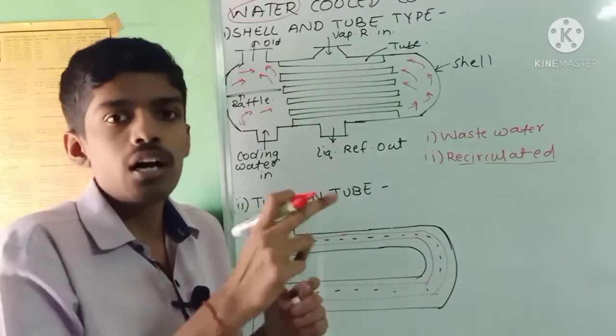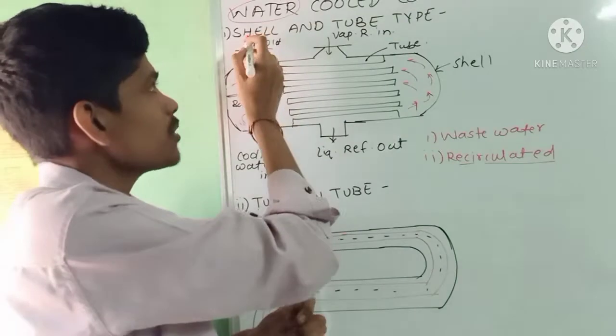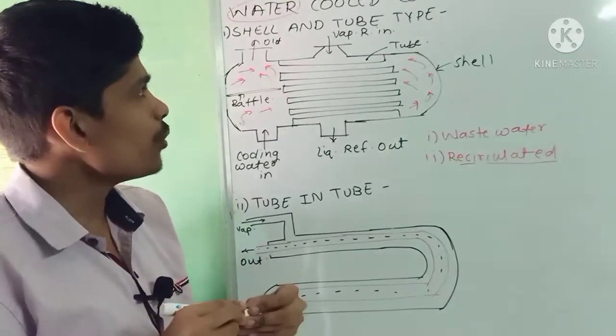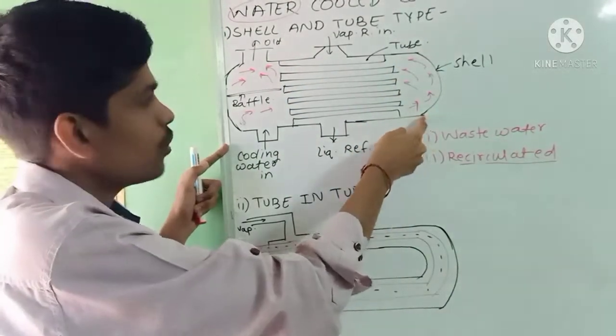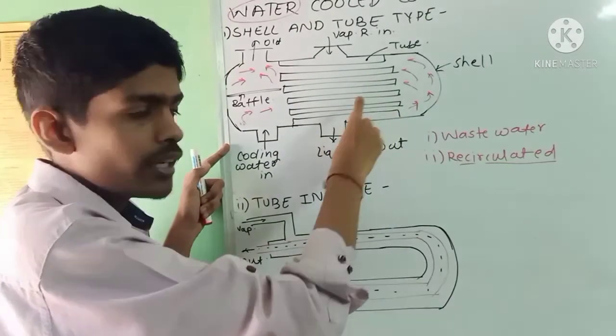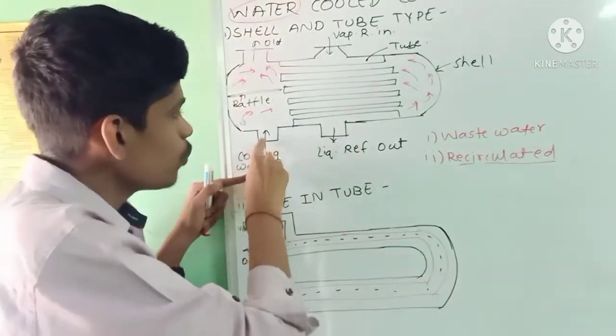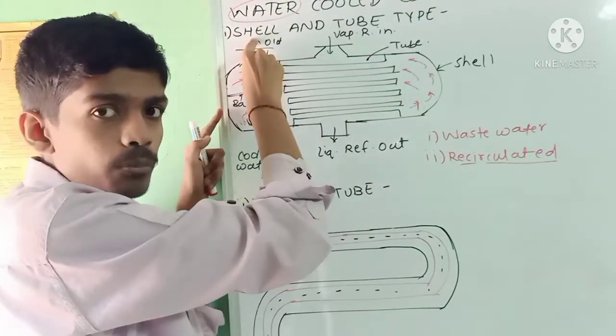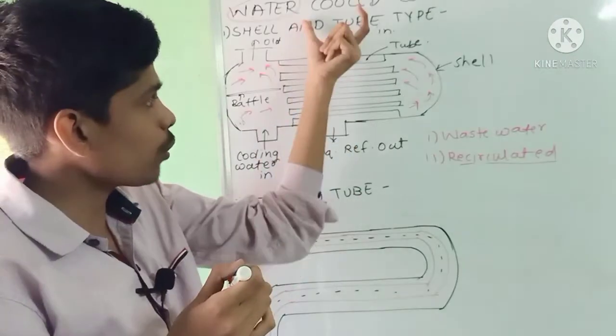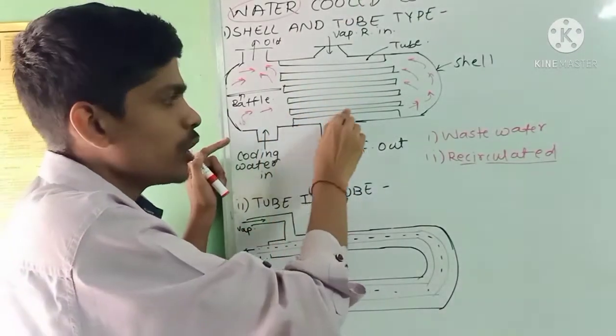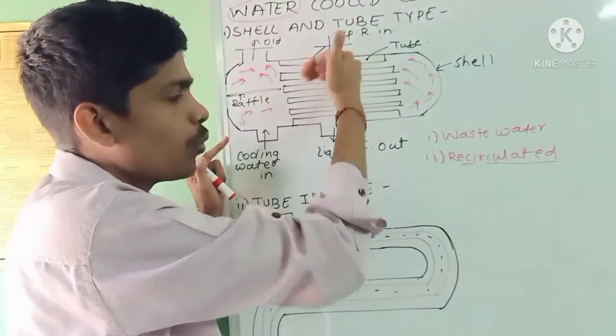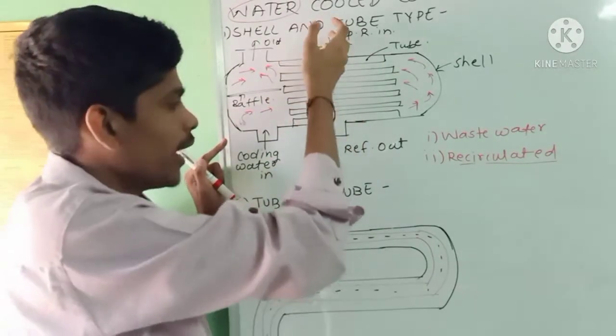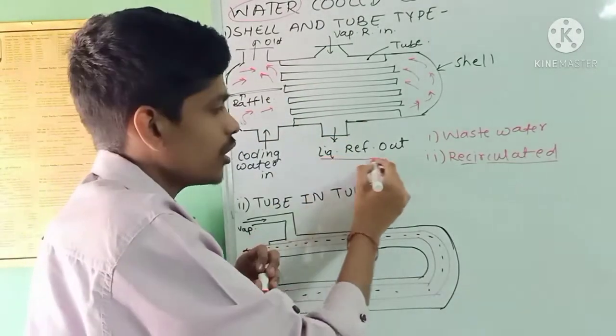There are three types of water-cooled condensers. The first is the shell and tube type. It consists of a cylindrical shell with a number of tubes arranged inside. Cooling water flows through the tubes, entering and exiting via baffle plates. Vapor refrigerant enters from the top and moves over the tubes. The cooling water absorbs the heat from the vapor refrigerant, which gets cooled and converted into liquid refrigerant.